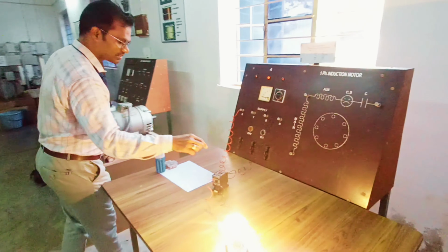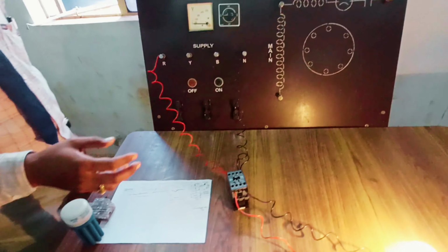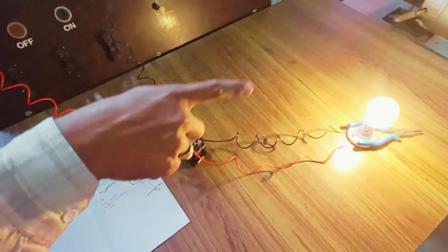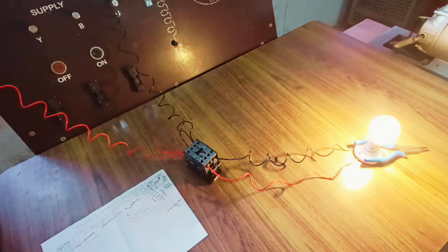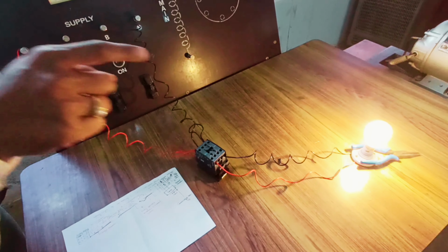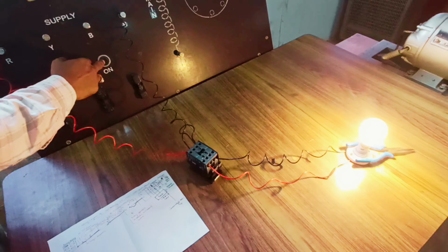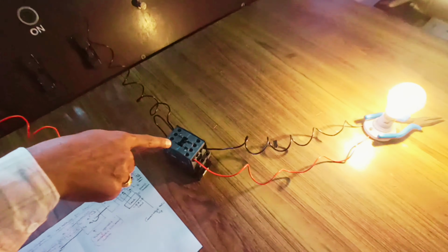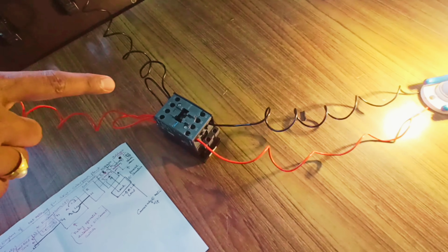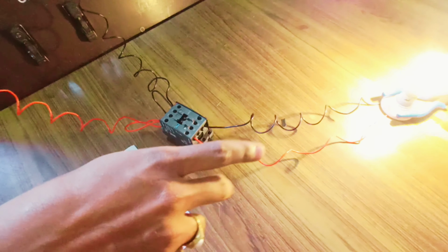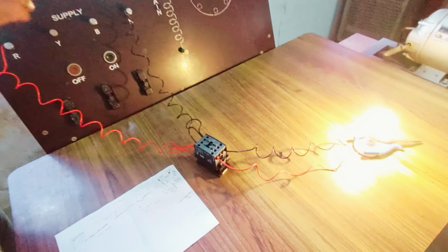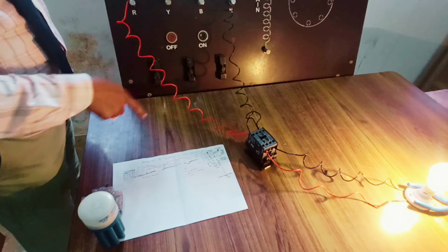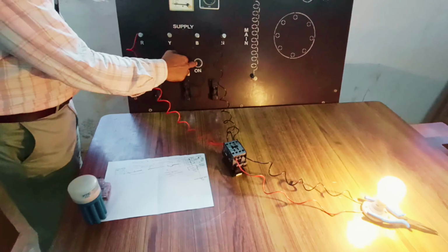Now the theme of this contactor is what happens whenever the grid has failed. Whenever the grid has failed, this contactor should open and the power should not be exported to the department. Why? Because the department will be working on the line. Now let us see how it works. Now you can see EB has failed. Carefully observe, the contactor has to trip. As soon as the contactor trips, the inverter cannot feed the power to the electricity board. This is one of the safety rules you have to follow in net metering of a 3 kilowatt solar PV system.